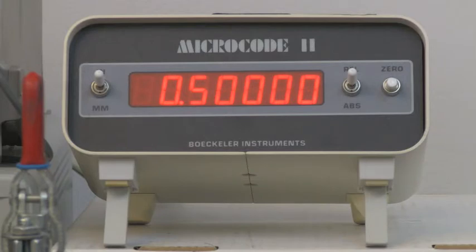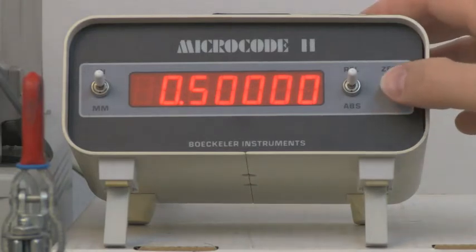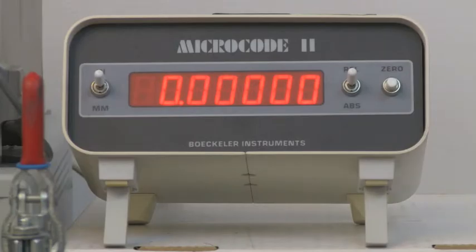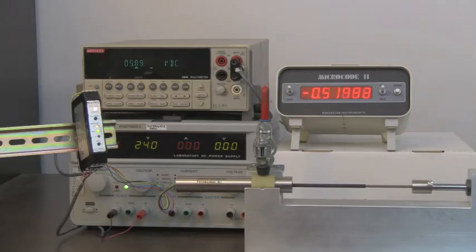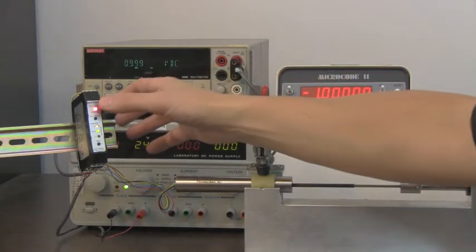We now reset the digital micrometer readout to zero. Next, we displace the LVDT by plus 1.0 inches. When the final position has been reached, we enter the full scale calibration point into the EasyCal by momentarily pressing the full scale push button.